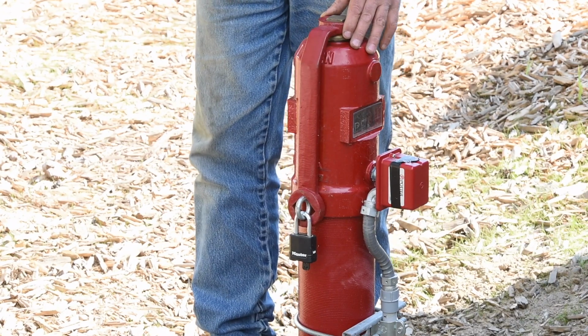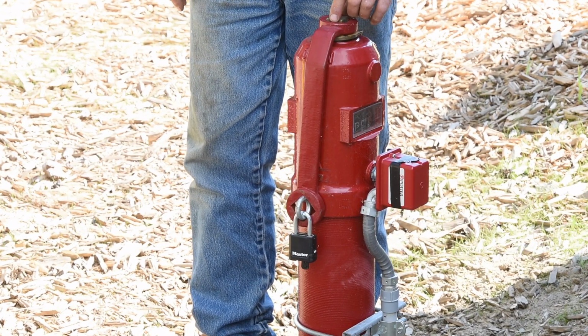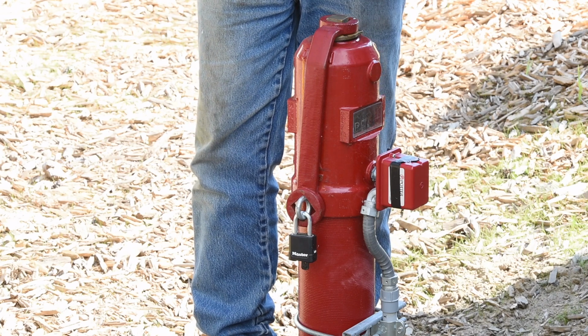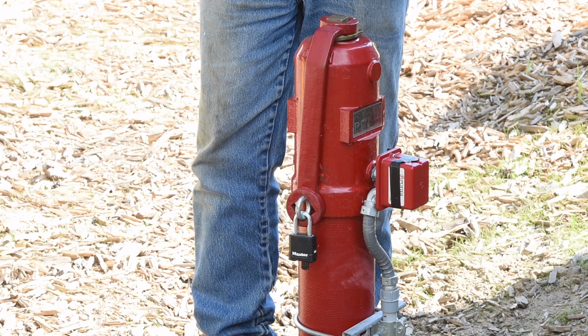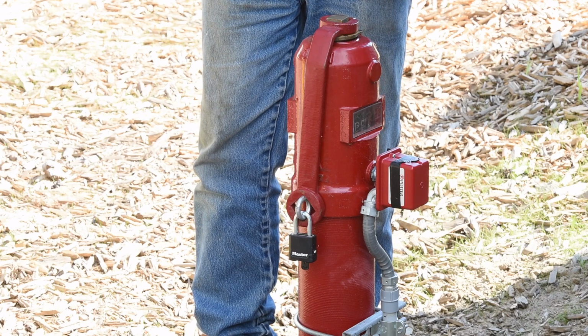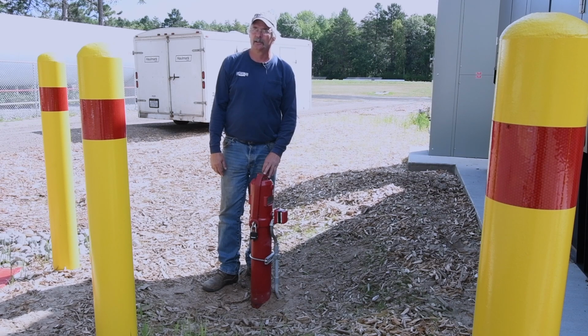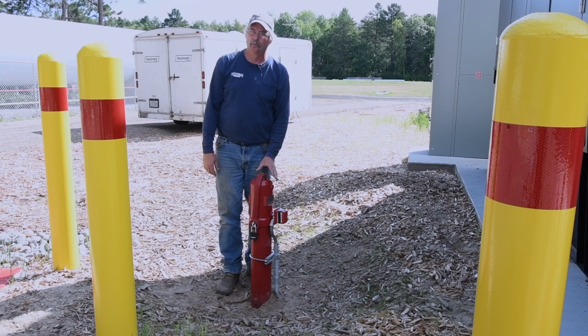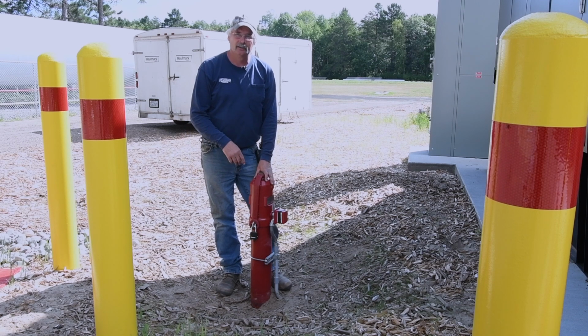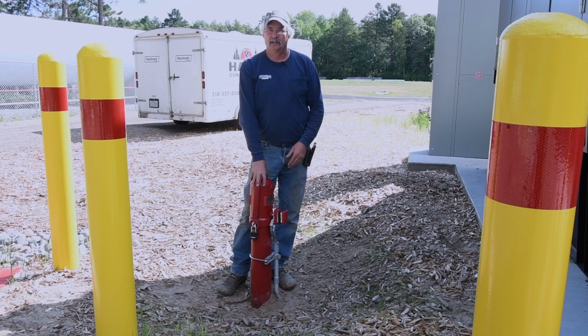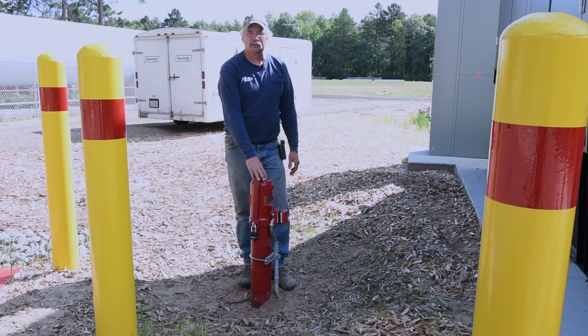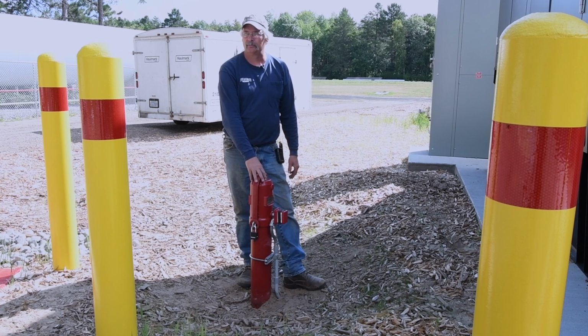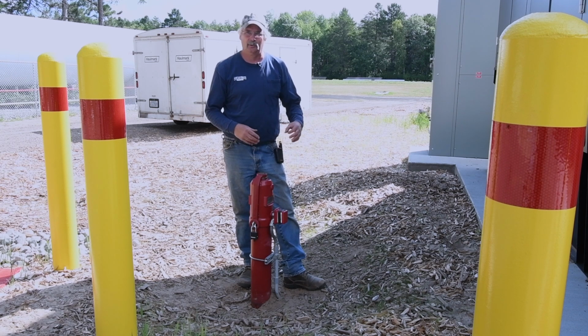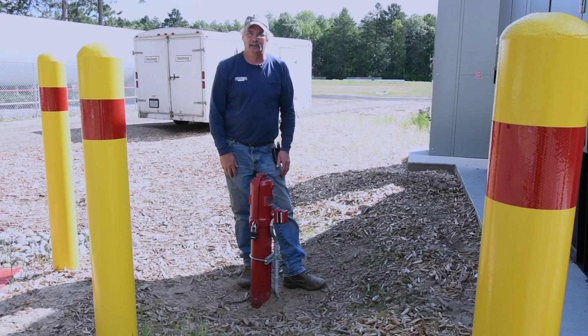And once again, during the annual inspection, what we do is we do a maintenance on these. We'd actually turn the valves, check the tampers, make sure it's turning free, dirt didn't cave into the post, and that it does come back into that panel properly. So that we know that when somebody does work on this valve and they shut it, that tamper switch picks up. Very important, because without the tamper switch, this valve could be shut or more than halfway shut, and then we wouldn't get the water supply into the facility that we need.